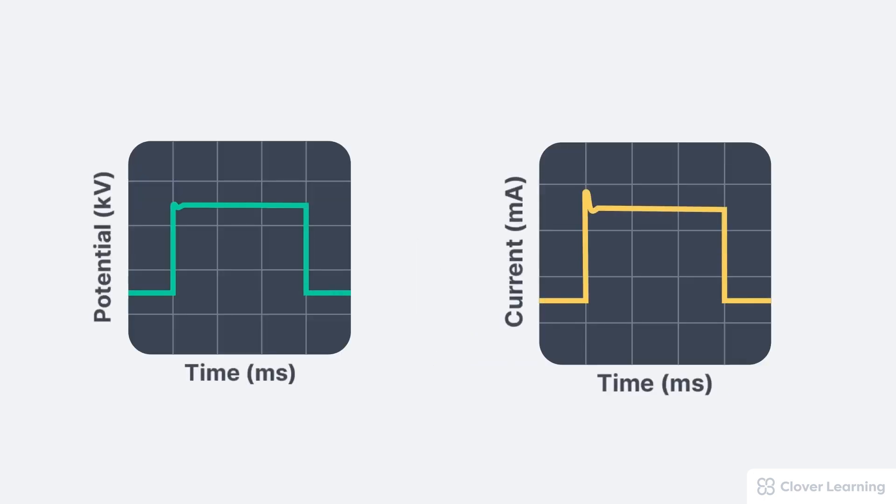So how do we know that the x-ray machine is actually generating the selected technical parameters during the exposure? One way is to measure the KV and MA waveforms. These waveforms are visual representations of the actual MA and KVP applied to the x-ray system during the exposure.